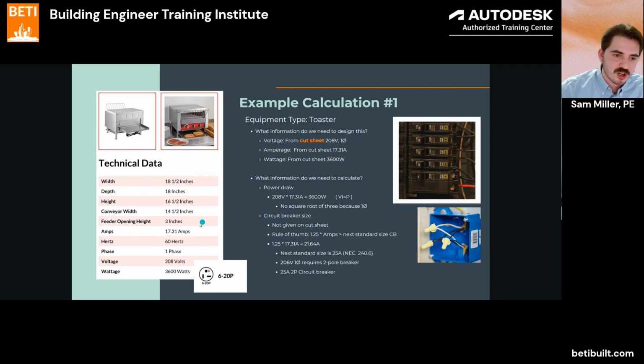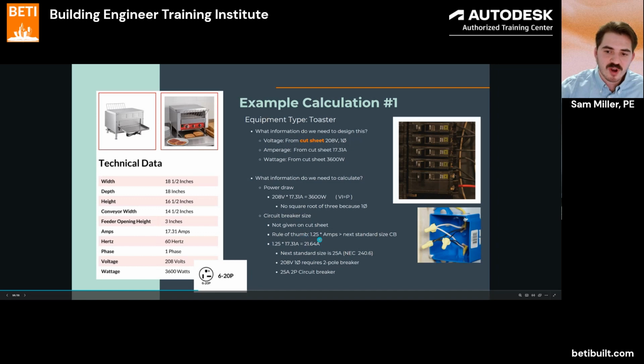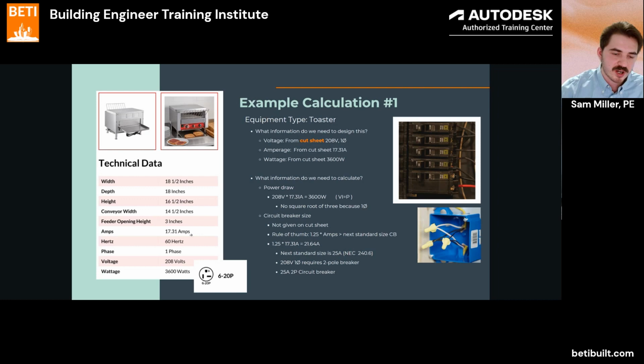It doesn't give that to us on the cut sheet. Some cut sheets will say MOP, MOCP, which is defined in these slides later, which I'll send out to you as a reference as you're doing your homework. But if you don't have something that tells you exactly what to use for your circuit breaker, the general rule of thumb is 1.25 times the amperage, and then use the next standard circuit breaker size. And the next standard circuit breaker size is something that you can go back and look at the cheat sheet that I sent you. I've also listed the NEC section, which lists standard circuit breaker sizes.